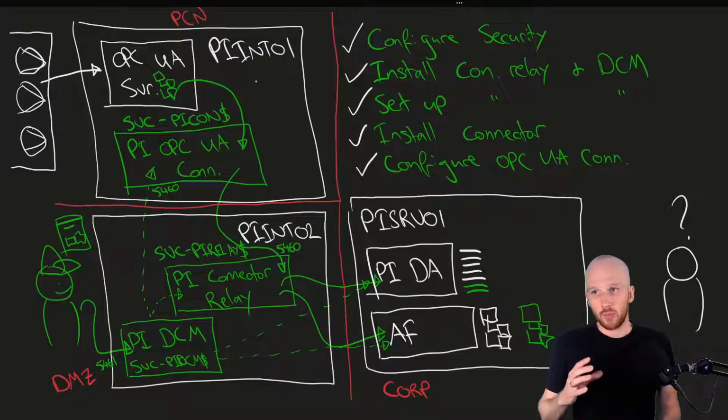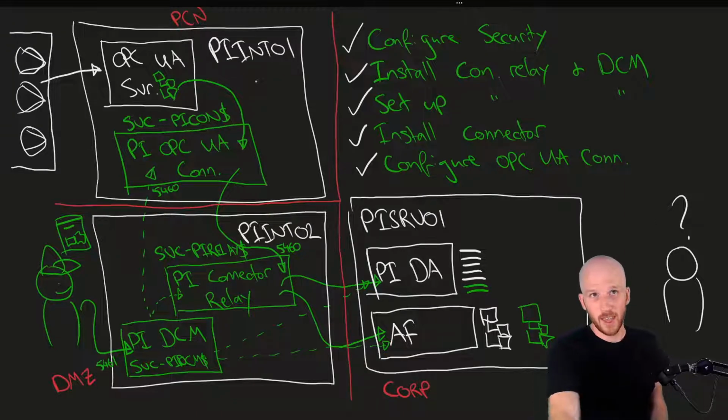So that's really the downside to a connector over an interface. Interfaces do support redundancy, and if you use OPC HDA, you can recover history on demand. However, really connectors are the set and forget option here.